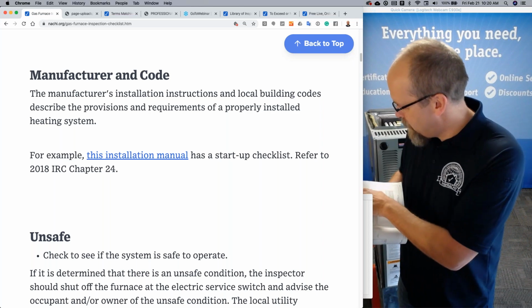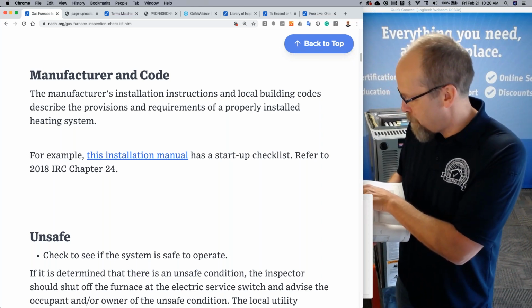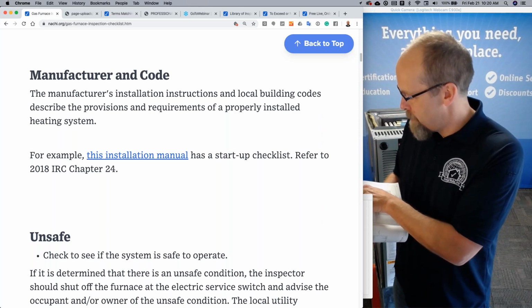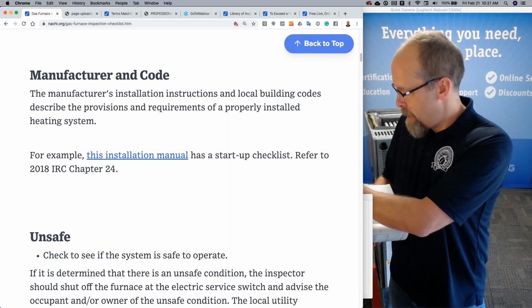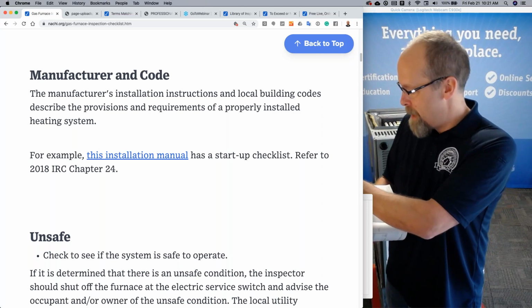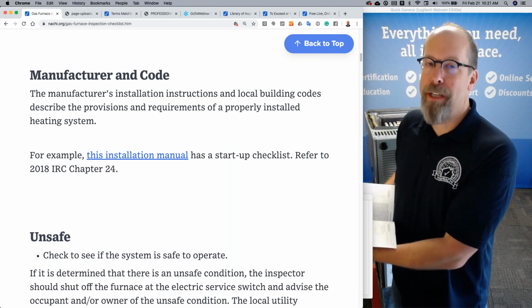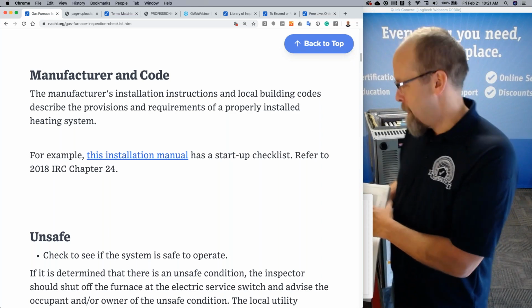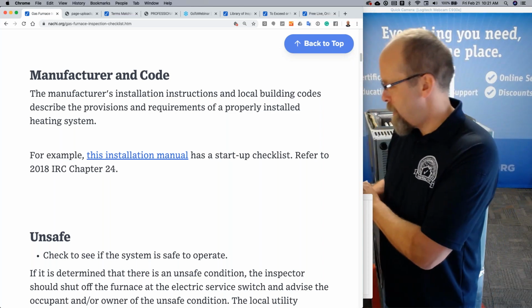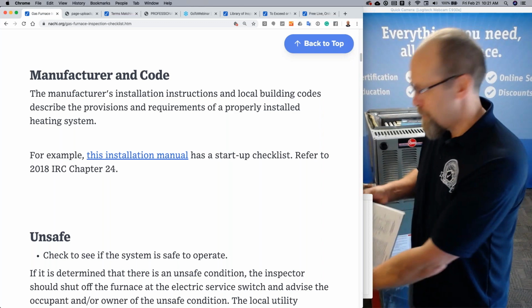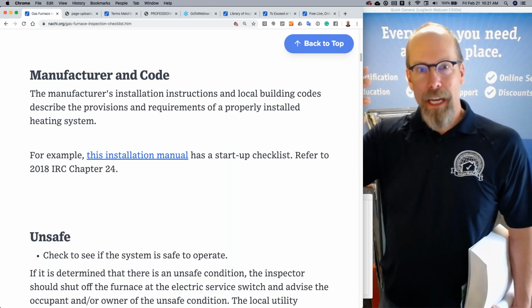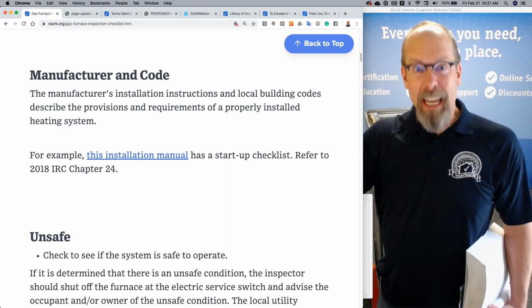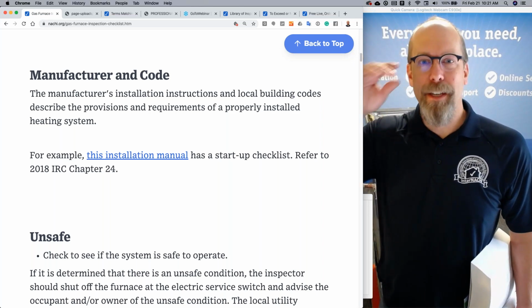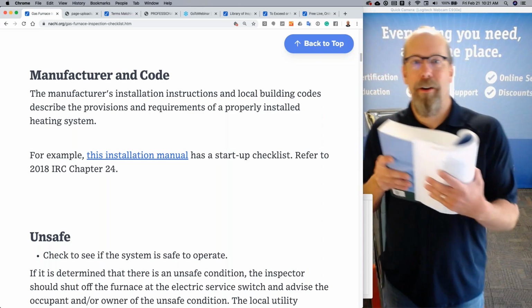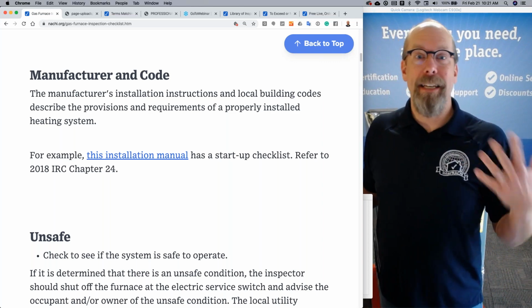I'll show you. The provisions in this section describe the requirements of combustion air that's necessary for the complete combustion of fuel gases, dilution of the flue gases, and the ventilation of gas-fired appliances and the space in which they are installed. An inadequate combustion air supply to gas-fired appliances can compromise safety by causing incomplete combustion, resulting in a couple of things, carbon monoxide. So we don't inspect combustion, dilution, ventilation of the systems, but I'm often wondering about the abnormalities that I may see around the heating system itself and wondering: is this thing venting properly? Does it have enough combustion air? And what is the space around it?